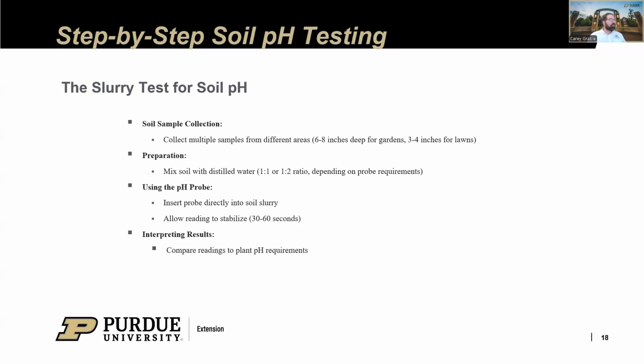So you're going to mix that with distilled water. Read your probe instructions. It'll tell you how much to use. So it's either 1 to 1 or 1 to 2. But typically, I've got a cup, I've got my soil in it, I'm going to add the water, and I don't want it super, super loose with water. I'm just trying to make a little bit of a mud, a slurry. And I want to be able to create a divot in the soil that fills with water that I can stick that probe down into. And that's where I'm going to take my reading.